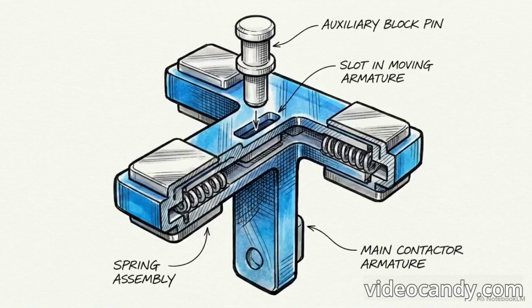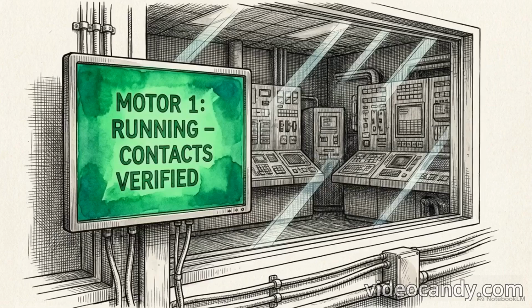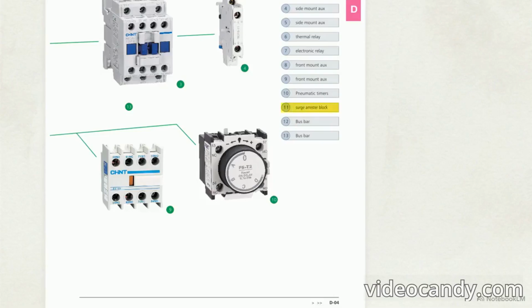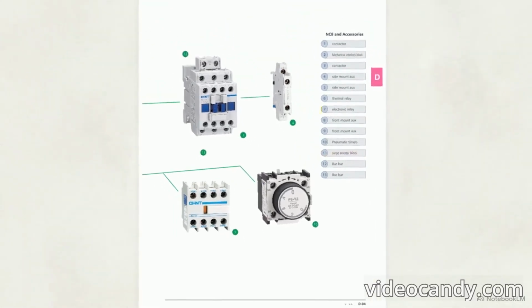This exploded view maps exactly where these auxiliary components physically integrate into the base frame. Items 5 and 8 represent the side and front mount auxiliary switch blocks, containing smaller internal contacts. Because these auxiliary blocks are mechanically linked to the main armature, they mirror its exact physical movement. This provides the PLC with a reliable, low-voltage verification loop, confirming the main contacts have successfully opened or closed. Other modules, like surge arresters, damp voltage surges at the coil, protecting sensitive PLC outputs.